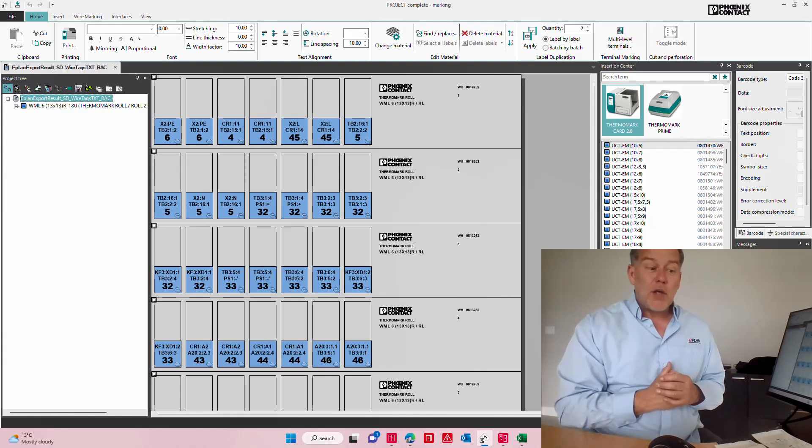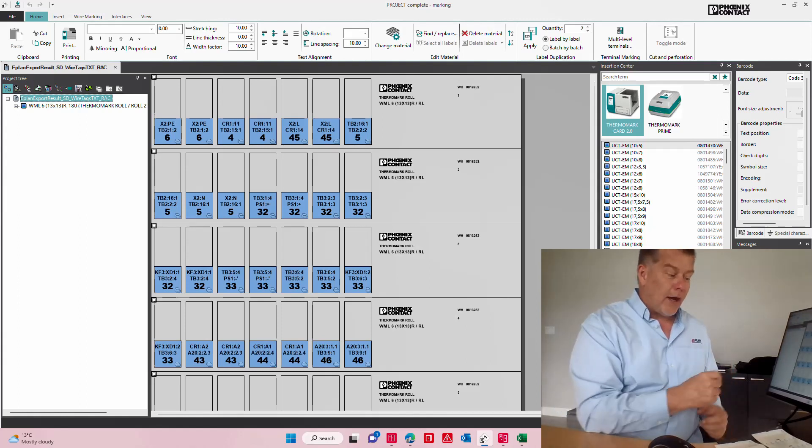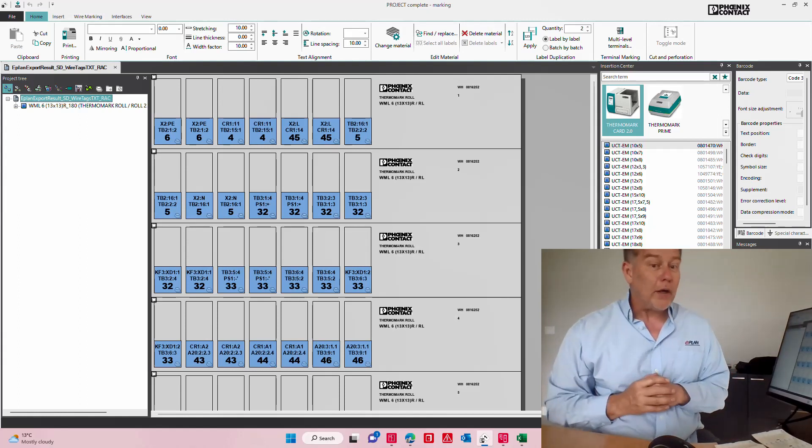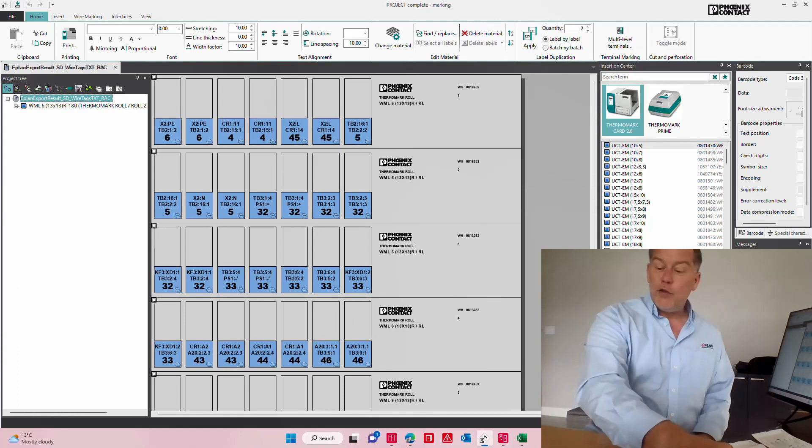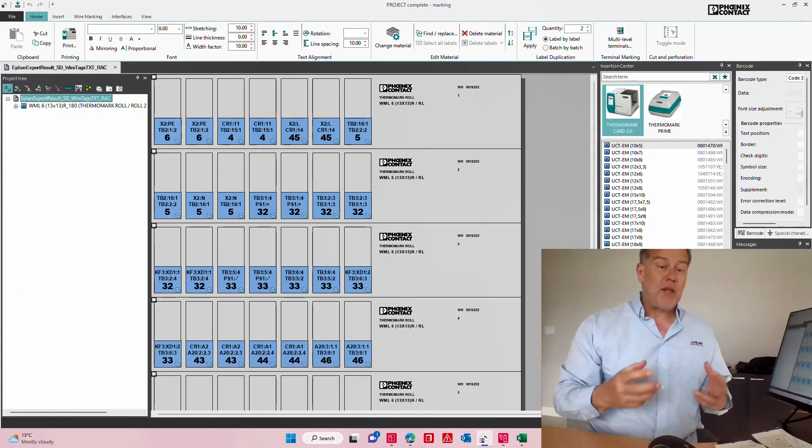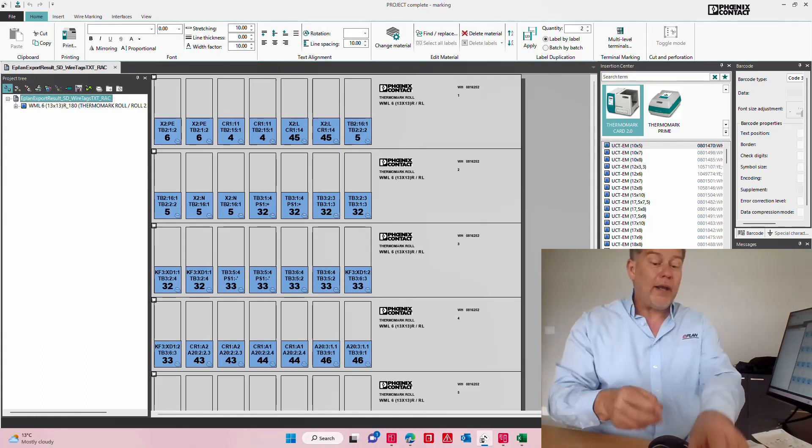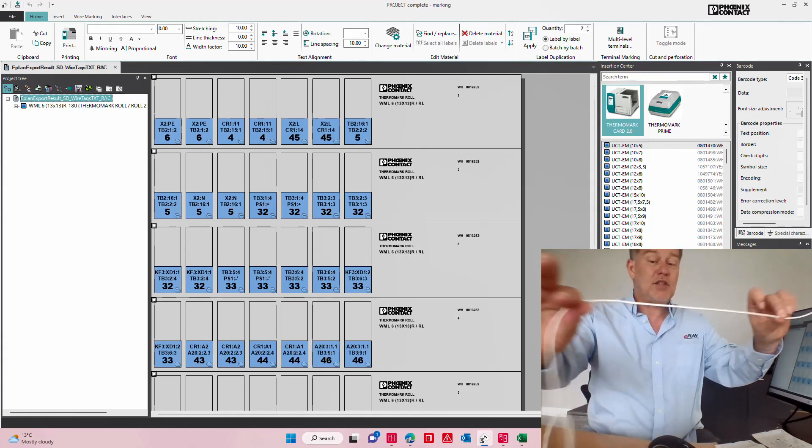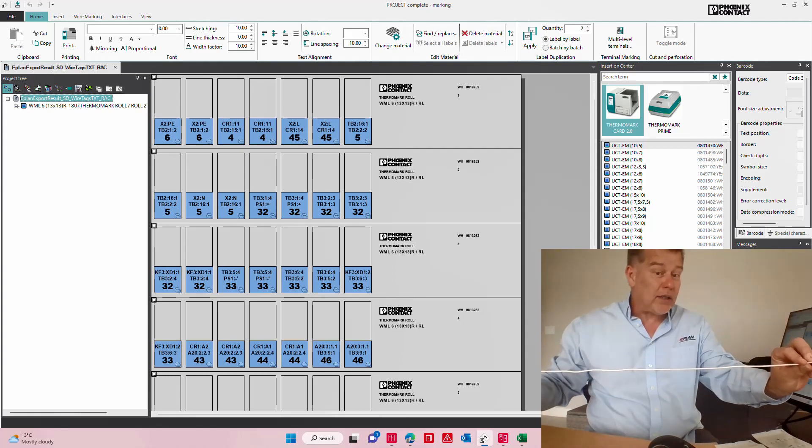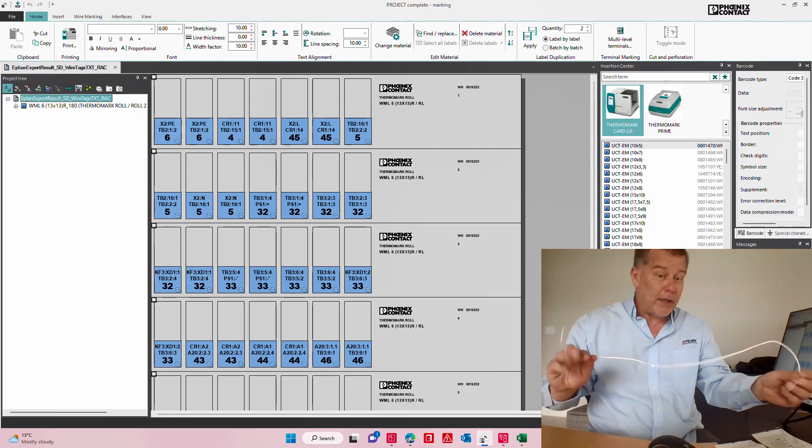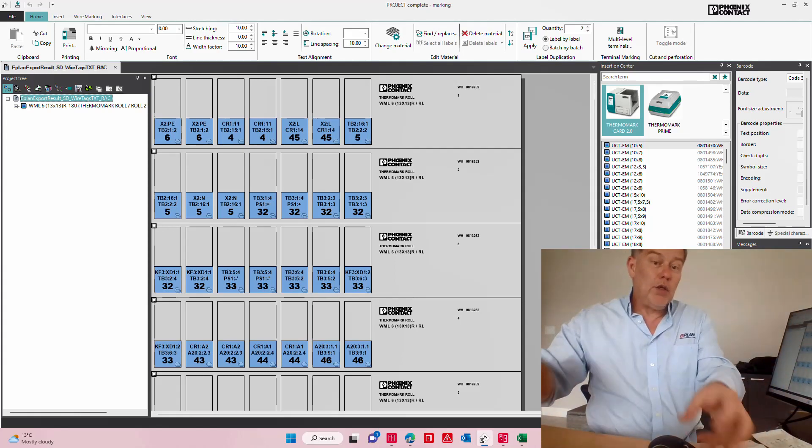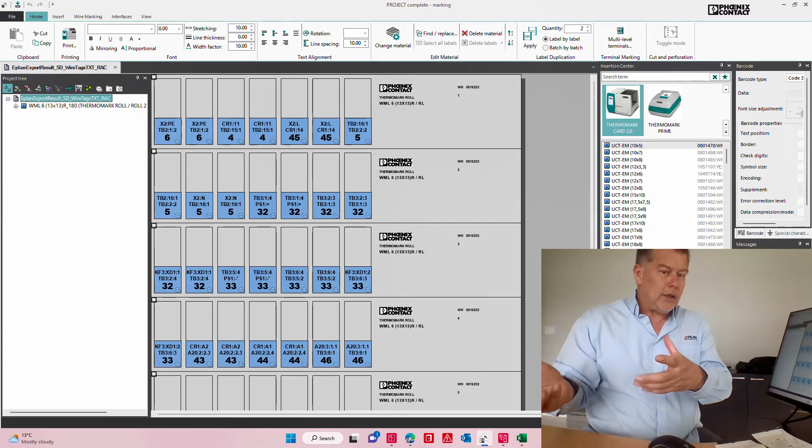I chose to print source and target and wire number to make it a little bit more comfortable later down the road. If I prefabricate the wires, if I do white wires, I have to make sure that this white wire that has a specific length that was calculated from EPLAN goes to the right source and target.